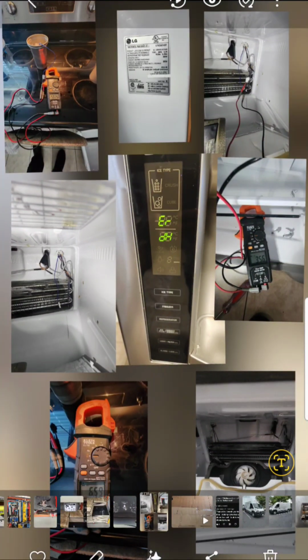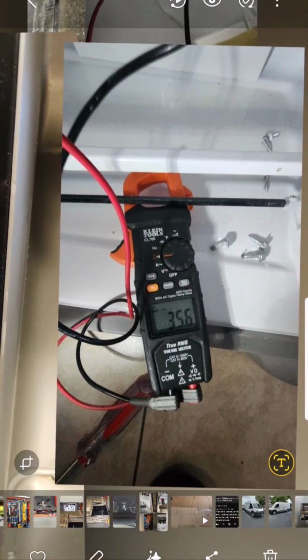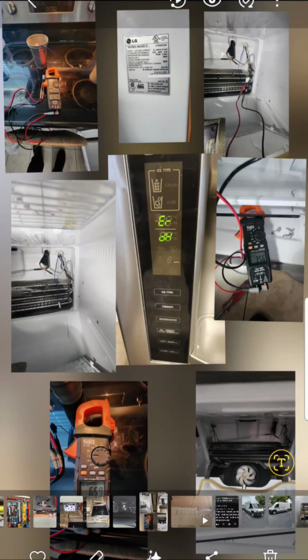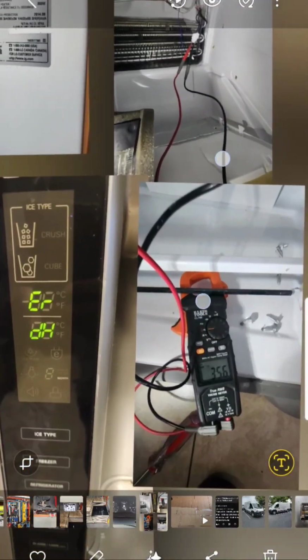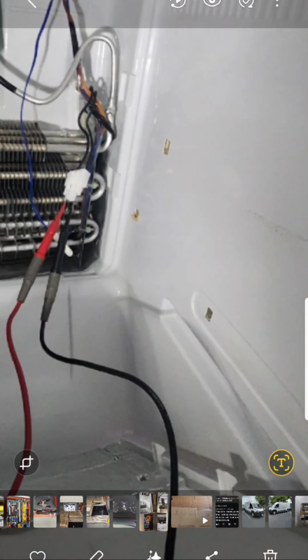So then I went ahead and I tested out the defrost heater, placed my probes on the defrost heater and checked across there, and I had good continuity there. Right here is the terminal for the defrost heater. As you can see, I have my probes in there in place, and I did get good continuity.